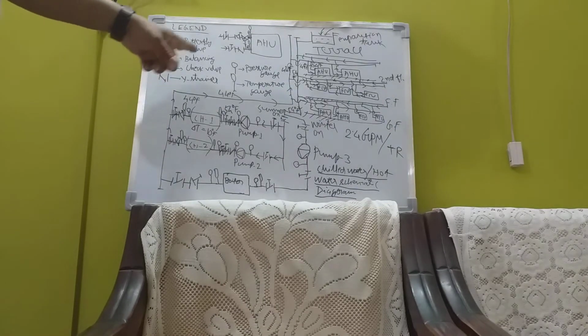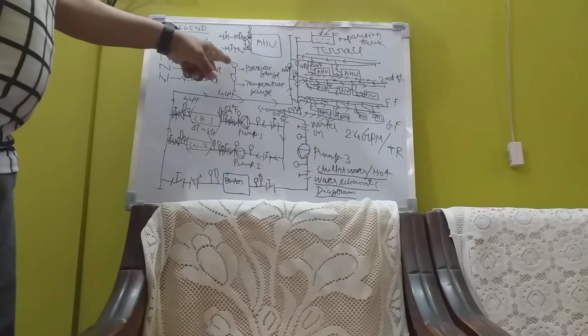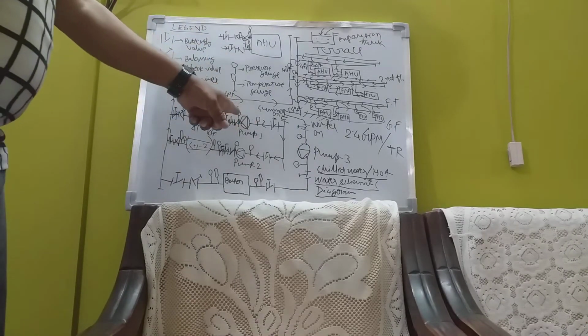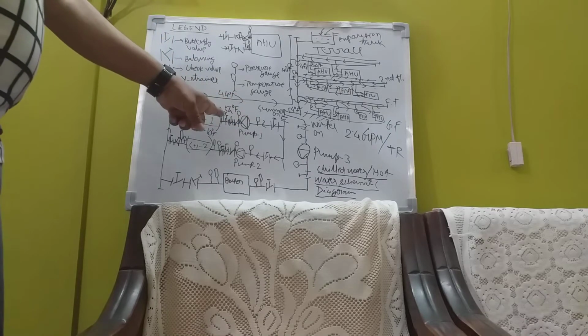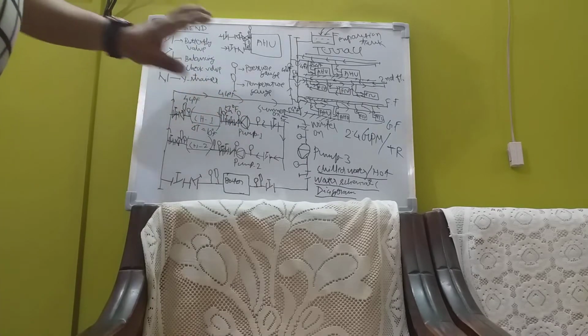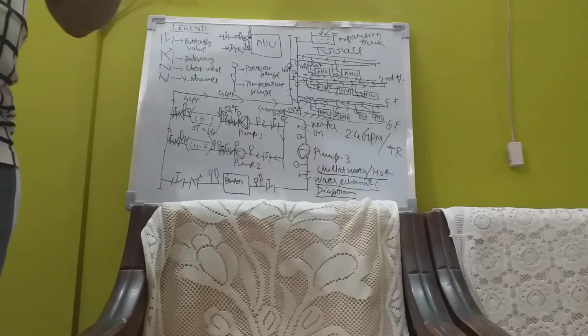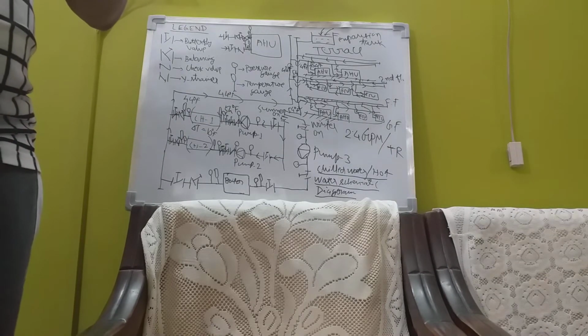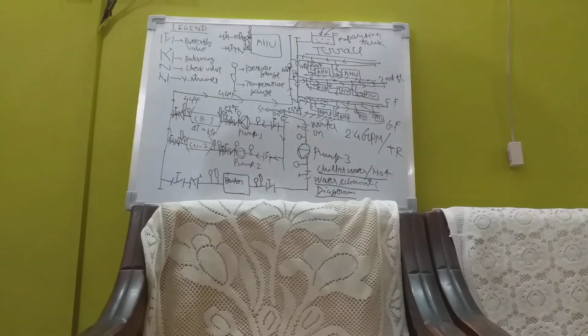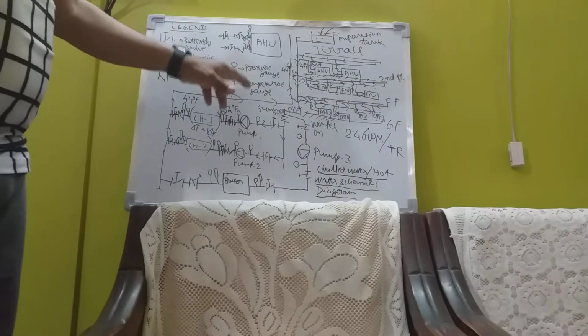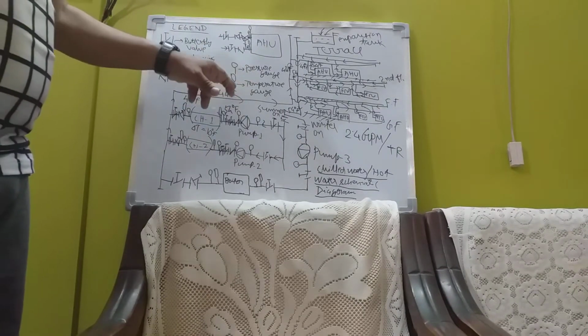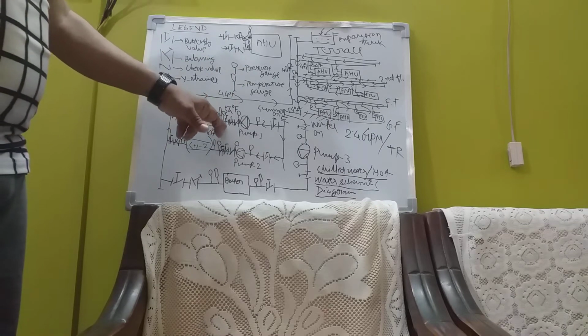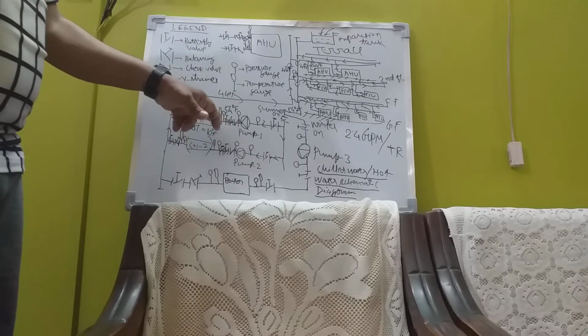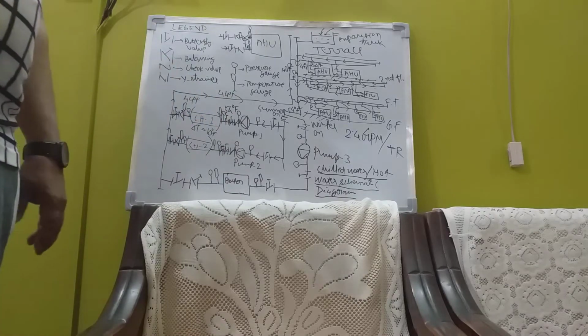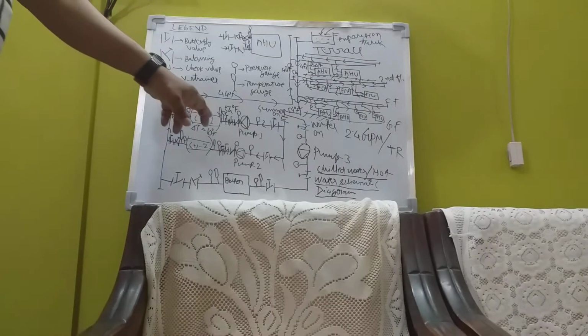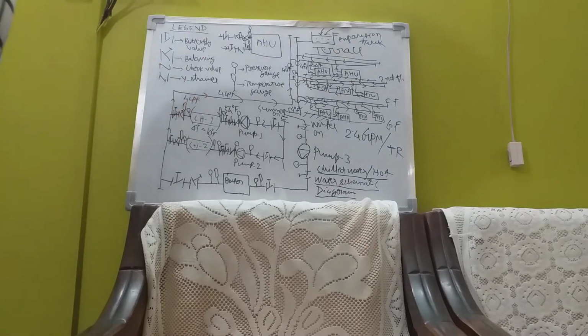Now, other than the balancing valve, we have pressure gauge and temperature gauge. This is the pressure gauge at the inlet and outlet of the pump, and pressure gauge and temperature gauge at the inlet and outlet of the chilling machine. In case of the pump, we don't need temperature, we need pressure, because the pump basically deals with water pressure. So for that reason, in case of the pump, we are putting a pressure gauge. In case of the chilling machine, we need both: what is the pressure drop across the chilling machine, and what is also the temperature drop. So both can be measured by pressure and temperature gauges at the inlet and outlet.